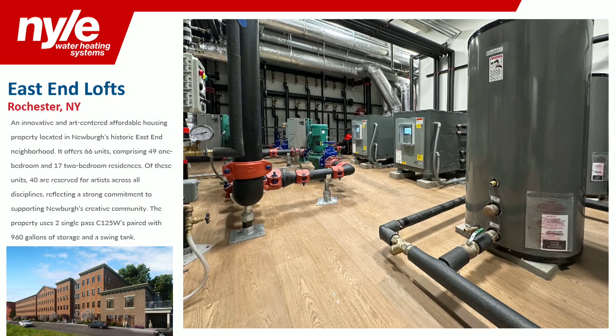They are 2 single pass units, so I think the last presentation may have led people to believe that variable large delta T is something that's exotic and brand new. And I know for a fact that most of the people up here that are going to talk to you today all offer units in this space, and I've personally been shipping units for about 7 years that do that. So single pass is what it's called. That is a viable option for domestic hot water generation, basically producing set point water for your application. This particular system has 2 single pass C125s paired with 960 gallons of storage and a swing tank.